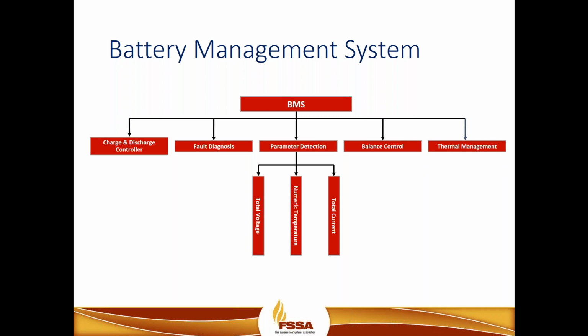So if you were to apply that type of technology to larger applications, say like energy storage systems or power generation facilities or systems, the BMS is critical, and it's looking at many different types of variables that lead to a thermal runaway event. So increasingly, the BMS system has a daunting task of identifying possible abuse factors and eliminating those risk factors before they become a thermal event. However, because of the advancements in the technology and the rapid pace at which the industry is evolving, the BMS system needs additional support to help prevent thermal runaway.